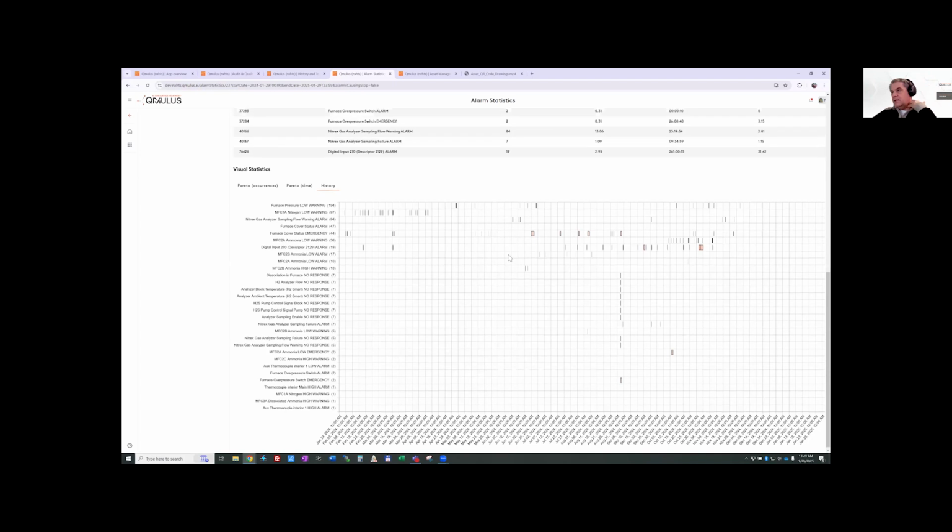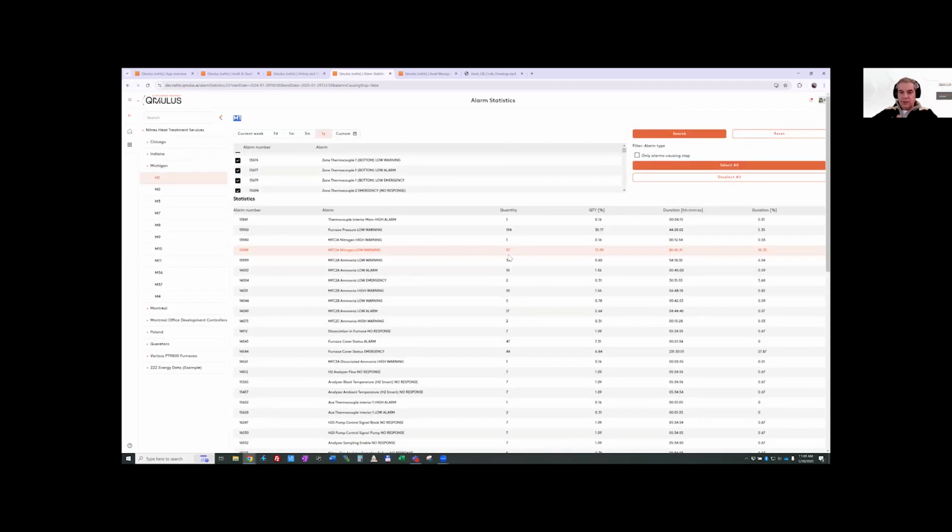So I have basically come to the conclusion, like I just summed up what Mike was trying to say. I got my part. I used my quality data to tell me what cycle is most likely a good candidate. I then go in and analyze that particular recipe in that particular furnace. I analyze my statistical analysis, and will it give me the results I want? And finally, I go look at the actual asset, and are there any issues lately that I might be worried about?